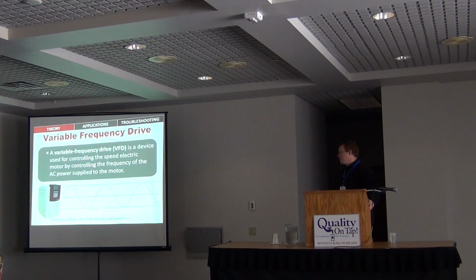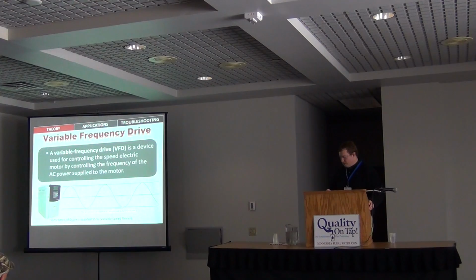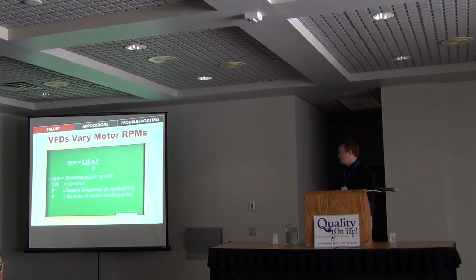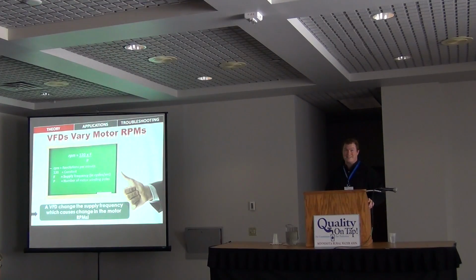Voltage doesn't matter. What a variable frequency drive does is control the speed of your motor by controlling the frequency of the AC power supply. So we want to change the speed of this signal. How do we do that? With this equation. By changing the cycles per second, or the frequency going into the motor, we vary the motor RPM. The RPM of the motor equals 120 times the supply frequency divided by the number of poles. If we're running a 4-pole motor across the line, that's 120 times 60 hertz, divided by 4, which is an 1800 RPM motor. To slow that down, the only thing we can change is F, our supply frequency.